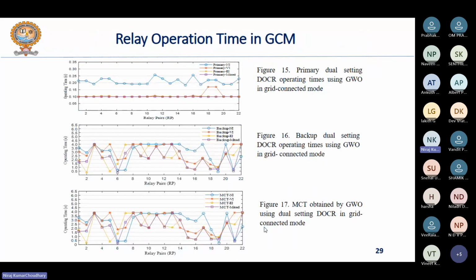Now, depending upon the calculated values of the relay settings, we have calculated the associated time of operation of the relays by putting the values of TMS, PS, and the relay characteristics identifier in the individual equation. You can see that in the first figure, the upper one, for all the primary relays, when NI characteristics, VI characteristics, EI characteristics, and mixed characteristics are used, then this is the time of operation of the relays. Here some overlapping is there, that's why I don't know whether you are able to see it or not, but there is a slight difference in the magnitude of time of operation, right?